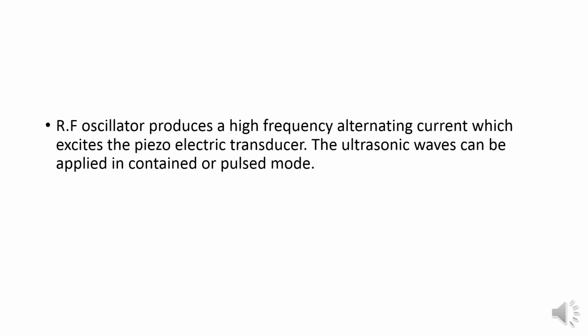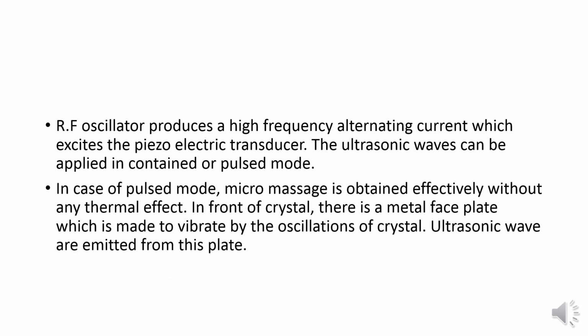The RF oscillator produces a high frequency alternating current which excites the piezoelectric transducer. The ultrasonic waves can be applied in continuous or pulse mode. In the case of pulse mode, micro massage is obtained effectively without any thermal effect. In front of the crystal there is a metal face plate, which is made to vibrate by the oscillation of the crystal. The ultrasonic waves are emitted from this plate.